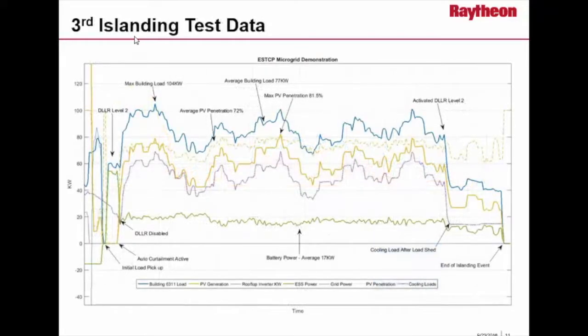So our third islanding test, the data looks a little different. Based on things we learned from the previous one, we modified some curtailment algorithms to make the battery usage almost entirely flat throughout the run. The average building load here was about 77 kilowatts, and the maximum PV penetration we reached was 81.5%, which is pretty significant.